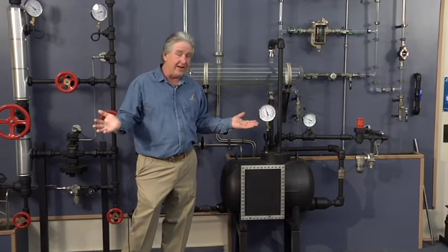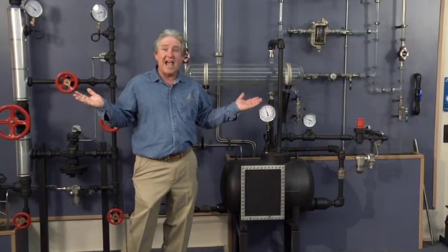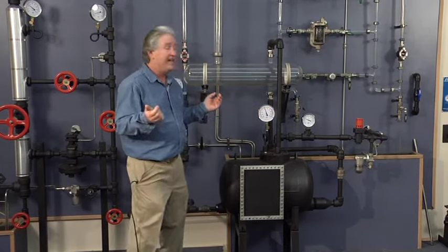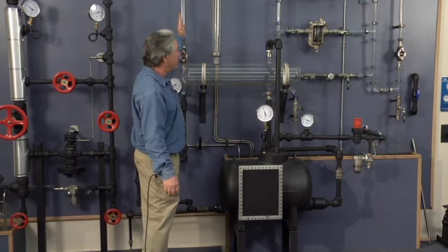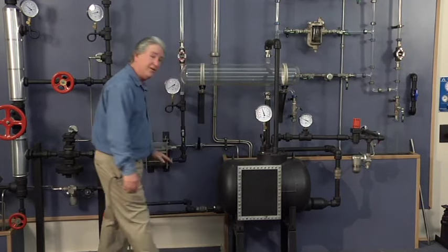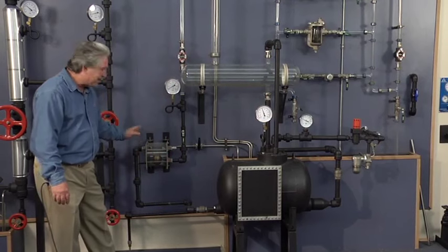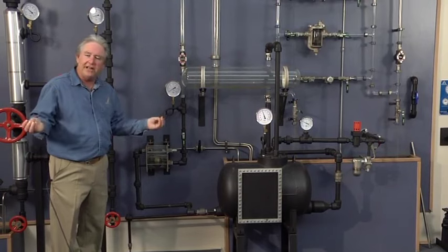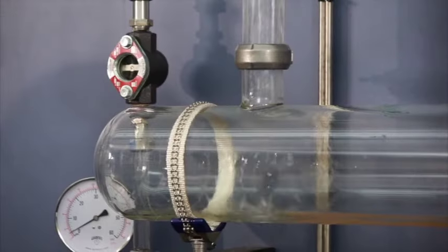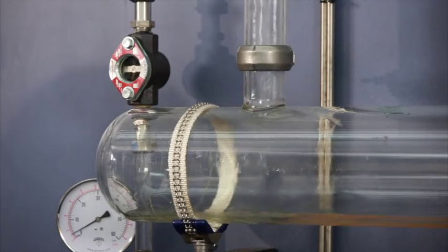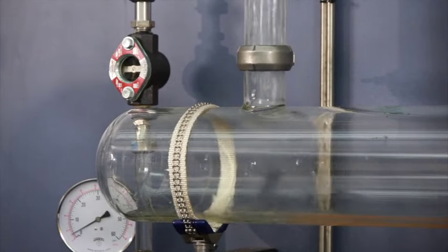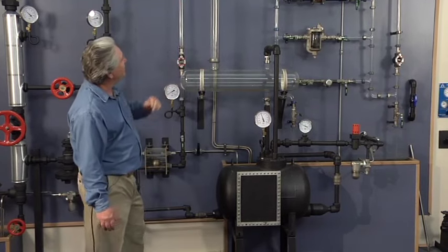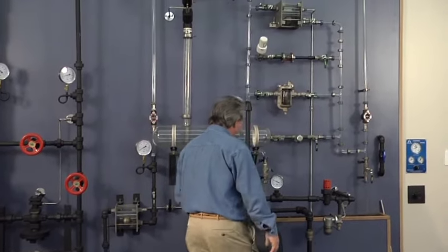But in essence, the technical term for it is there is lack of differential pressure. There is no pressure difference. If anything, we have more back pressure than we have inlet pressure to the trap. So regardless of how big this trap is, when there's no difference in pressure to push liquid through it, this trap will not operate correctly on this exchanger. So what we're doing is we're continually condensing in the exchanger. You'll see that we're at 4 pounds and 4 pounds.